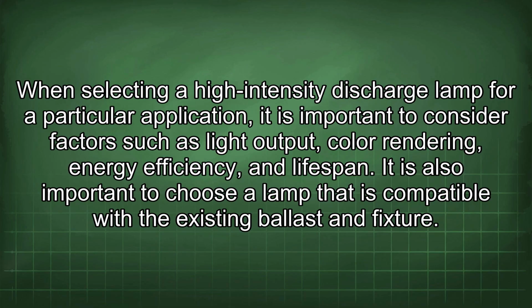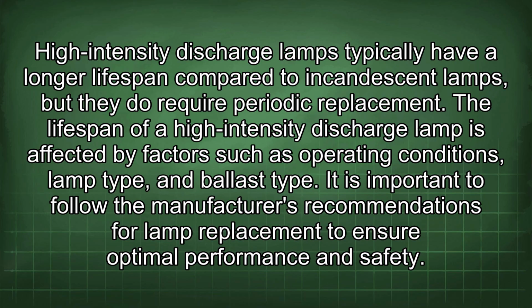When selecting a high-intensity discharge lamp for a particular application, it is important to consider factors such as light output, color rendering, energy efficiency, and lifespan. It is also important to choose a lamp that is compatible with the existing ballast and fixture. High-intensity discharge lamps typically have a longer lifespan compared to incandescent lamps, but they do require periodic replacement. The lifespan of a high-intensity discharge lamp is affected by factors such as operating conditions, lamp type, and ballast type. It is important to follow the manufacturer's recommendations for lamp replacement to ensure optimal performance and safety.